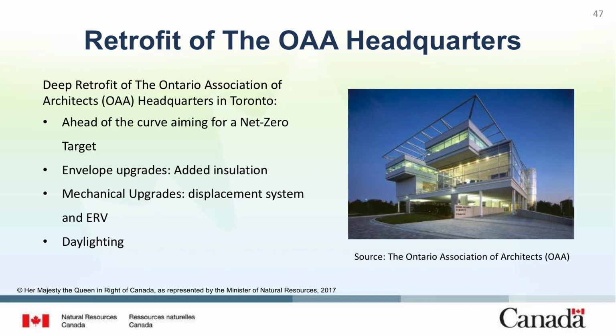The OAA wants to get ahead of the curve with their energy reduction targets by aiming for a net zero building. The first step in the building retrofit will be envelope upgrades to reduce the heating and cooling loads. According to blower door tests, the OAA building envelope scores very well for air tightness, but insulation can be added to further reduce the loads. Next, the team looked at the mechanical systems. The current mechanical system uses forced air heating augmented with reheat coils in each variable air volume or VAV box, and electric baseboard heaters. In cooling mode, the system cools air and then reheats it for each individual office. While this strategy was considered good when the building was built, it consumes a lot of energy. Also, after 20 years of service, many of its components are coming to the end of their life expectancy.